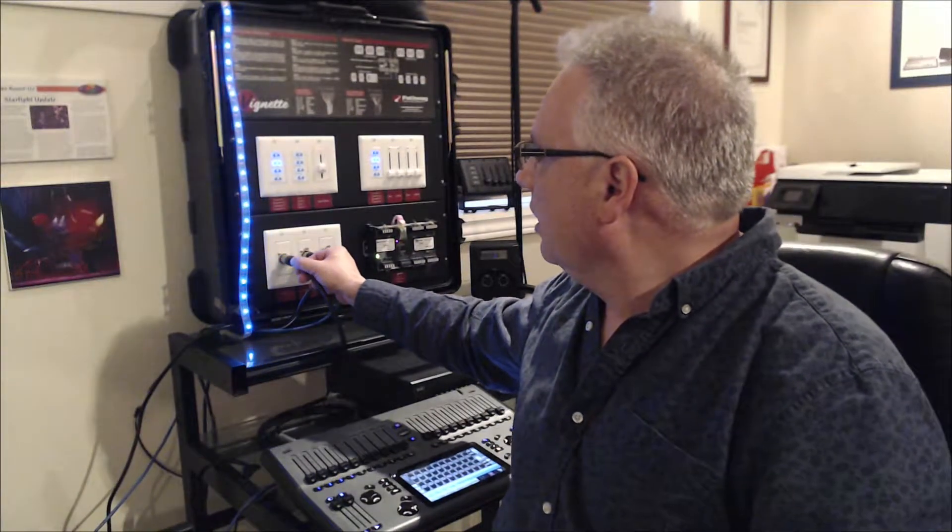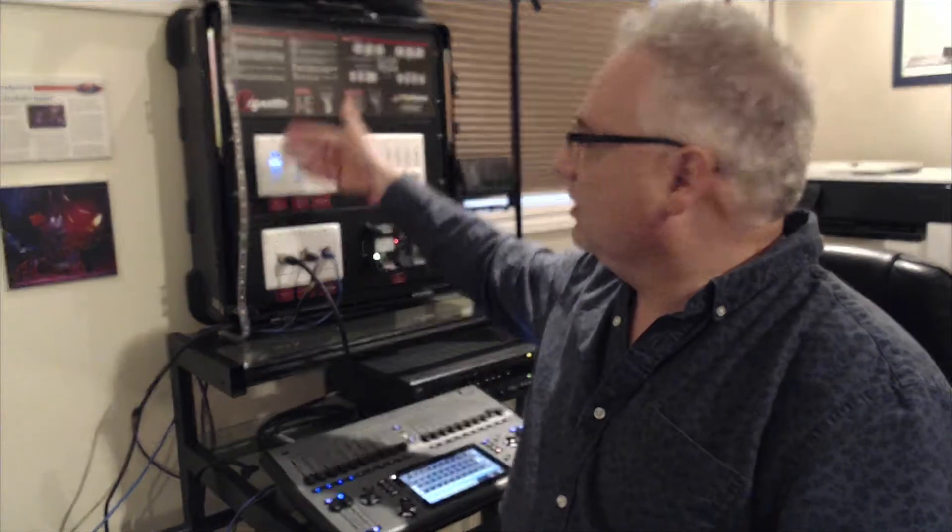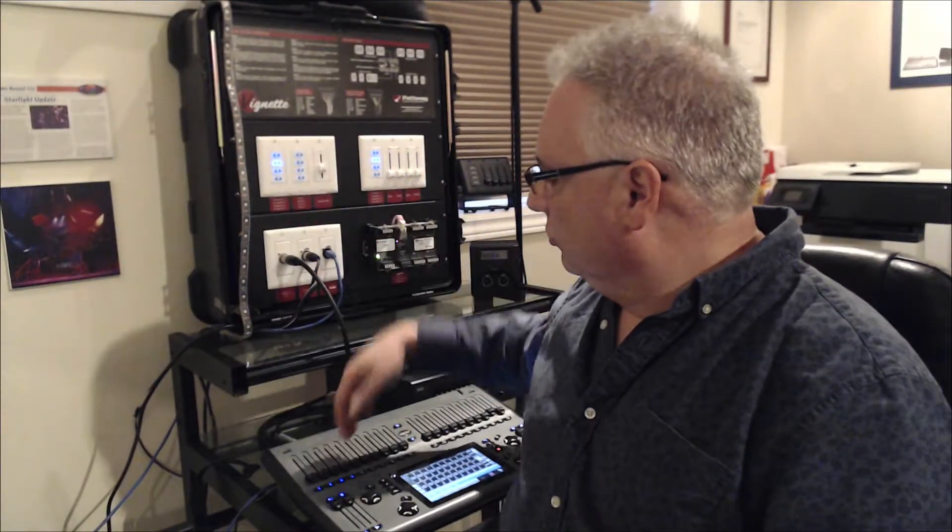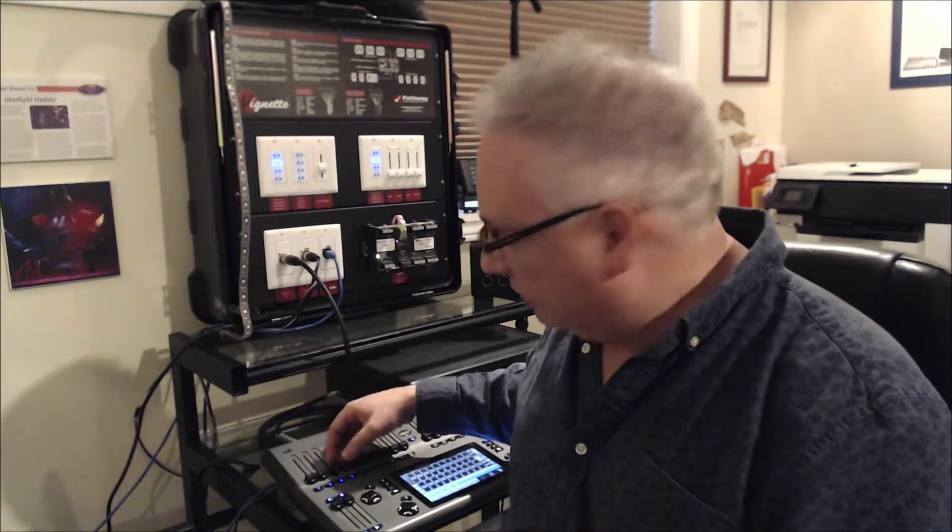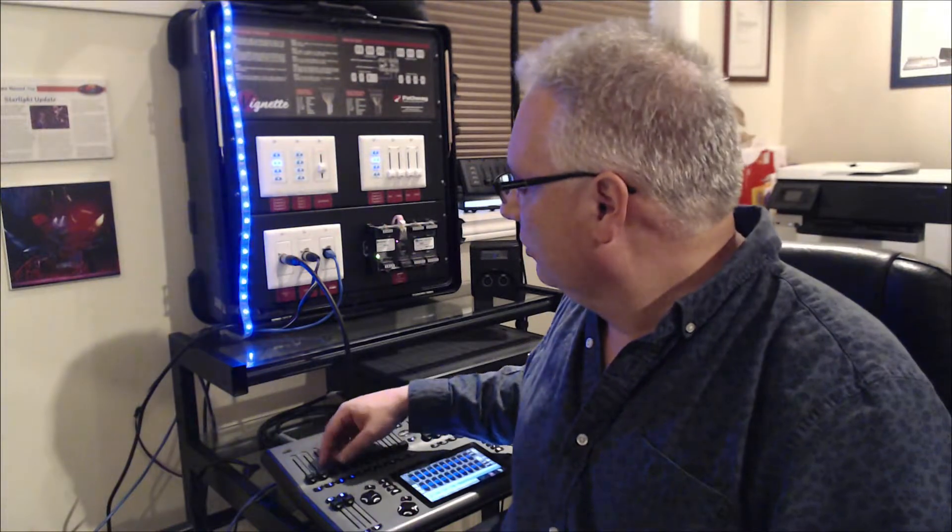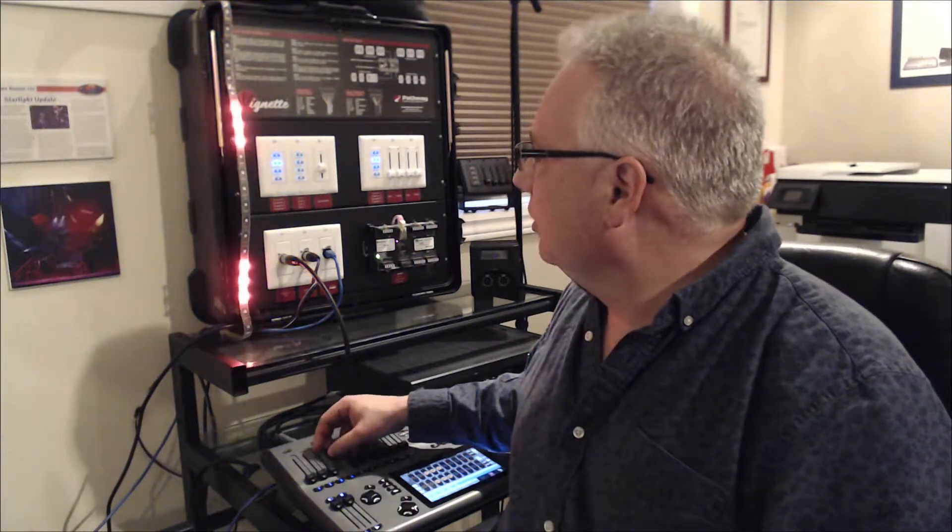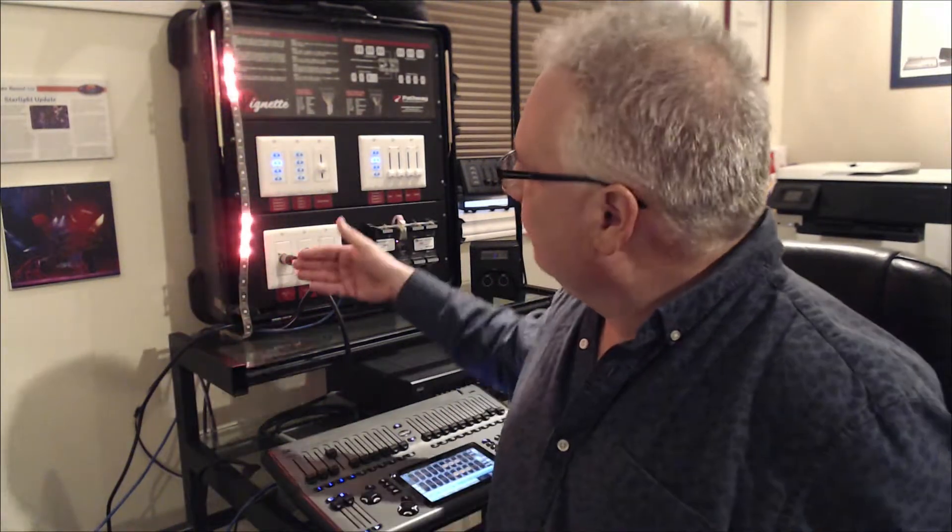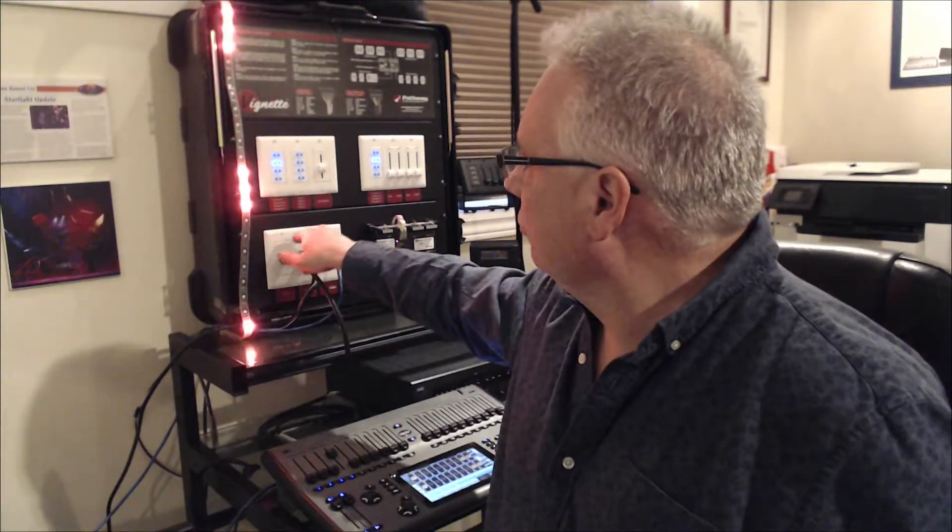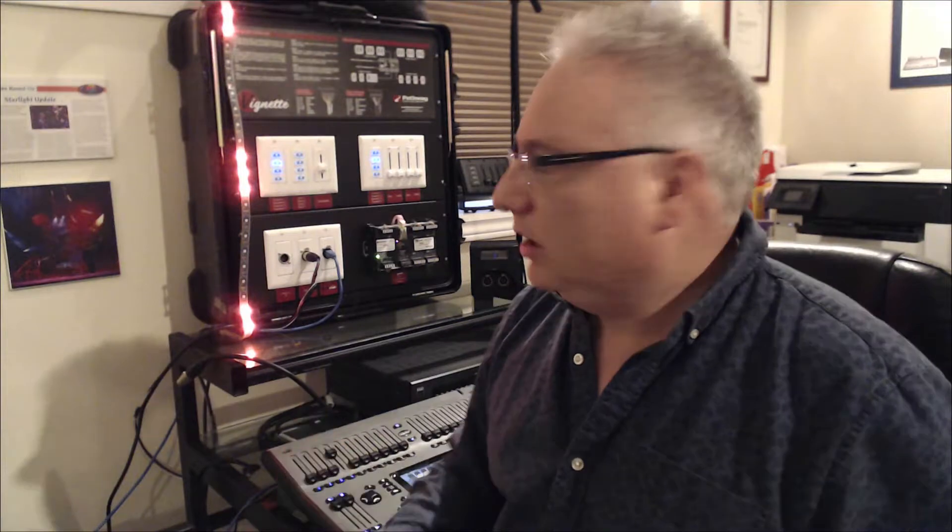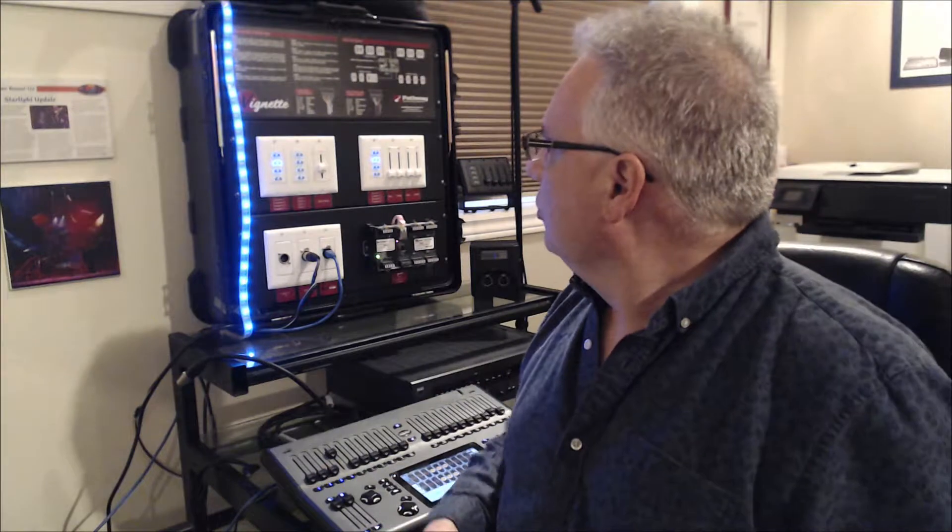But if a lighting console like this comes online by plugging it into the system, what actually happens is it yields control to the CogniTek in this case. Then you can run different looks live on your lighting console. So I built one here that is a bit of a chase, so we can see whenever you see the lights chasing like this we know the CogniTek's in control. And when you take it away by unplugging it, it's going to crossfade back to the Vignette snapshot system.